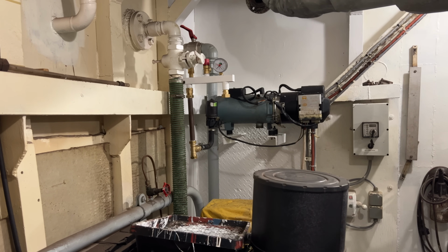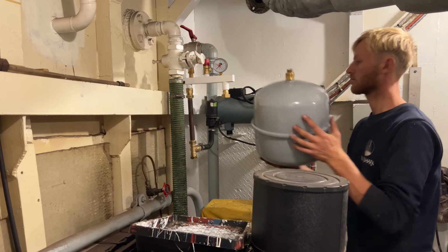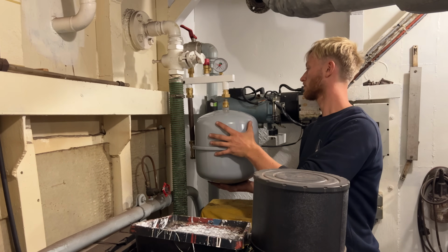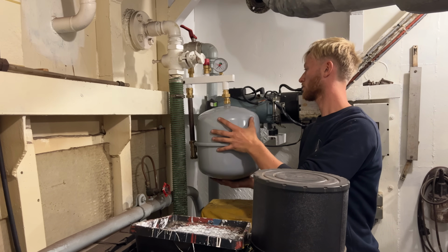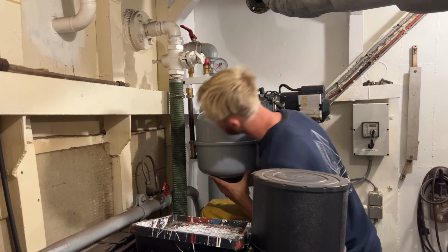Normally these diesel burners have a little header tank for static pressure on the suction side of the pump. But we're installing an expansion vessel which we can fill to a higher pressure, because we don't have that much height available.